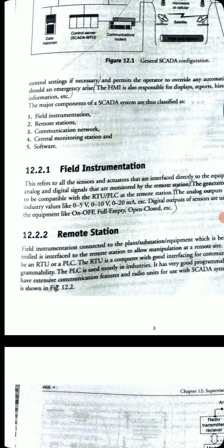Next is the remote station. The plant, substation, or equipment which is being monitored and controlled is connected through field instrumentation and interfaced to the remote station to allow manipulation of the remote site. The remote station may be an RTU or a PLC. The RTU is a computer with good interfacing, communication, and flexible programmability. The PLC is used in most companies and industries, and it has very good programmability. Modern PLCs also have extensive communication features and radio units for use in the SCADA system.